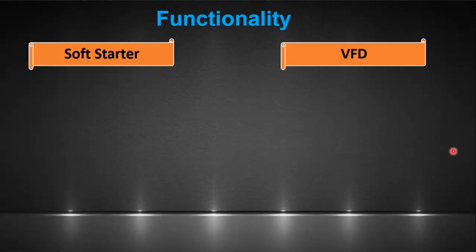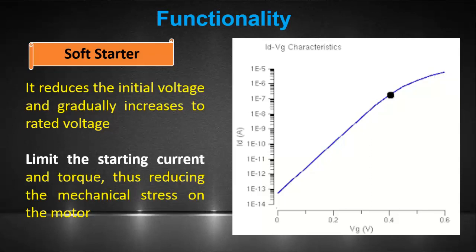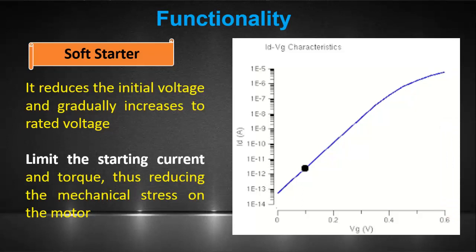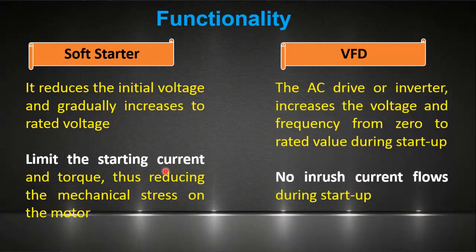Now we will see the main differences between these two motor control devices. A soft starter is a device used to reduce the initial voltage supply to the motor during startup, which results in low inrush current as compared to a DOL starter. By adjusting the firing angle of thyristors, the applied voltage gradually increases from zero to full rated voltage, helping to limit the starting current and torque, thus reducing the mechanical stress on the motor.